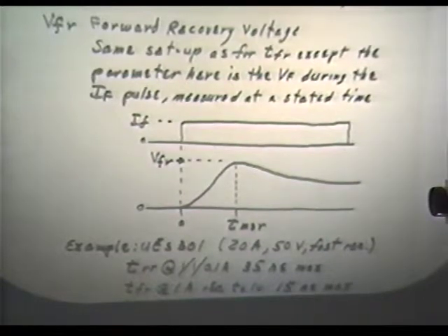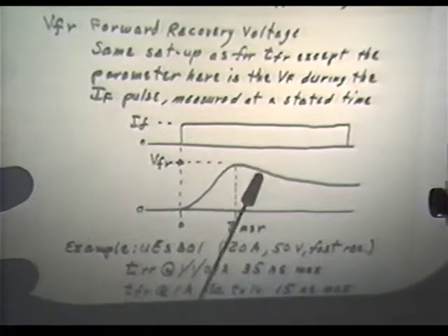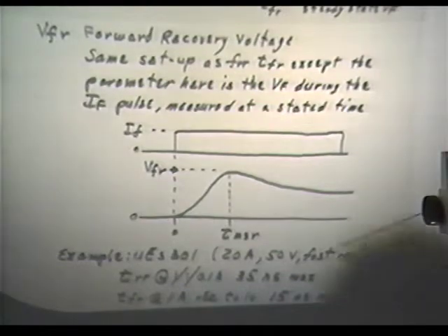And the same thing is true on how high the voltage went. Well, to try to not leave it open to operator interpretation, you set the time and say, whatever the shape of this thing looks like within reason, find that time and tell me the voltage. So, conceivably, this thing could do this. You see what I'm saying? It's not an absolute guarantee, but it's an approach that's been settled upon as something that can be done at a price that somebody's willing to pay to get some sort of control on that parameter.